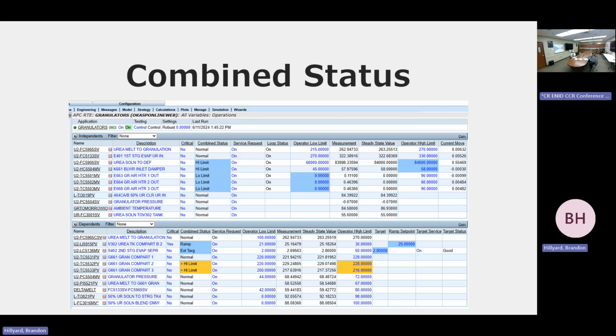So you've got 2 MVs at high limit, 3 MVs at low limit, and then you have 2 CVs that are at their targets, essentially. And so just by looking at this, you could maybe guess what each of these is constrained by. Obviously, the MVs at their own limit are constrained by their optimization target limits, but the other 2 are constrained by those CVs down below.